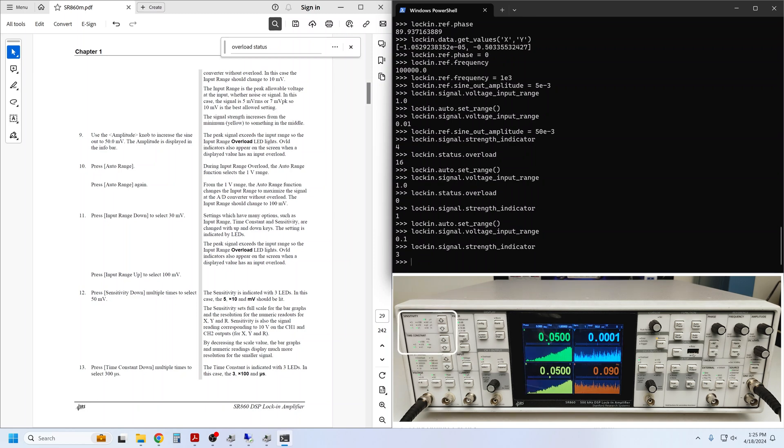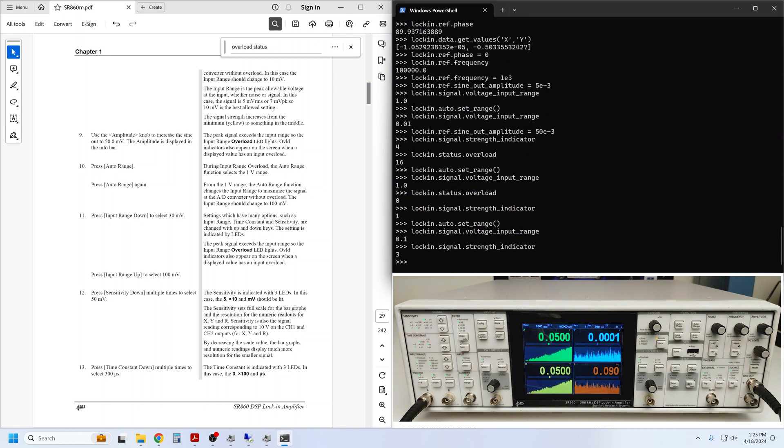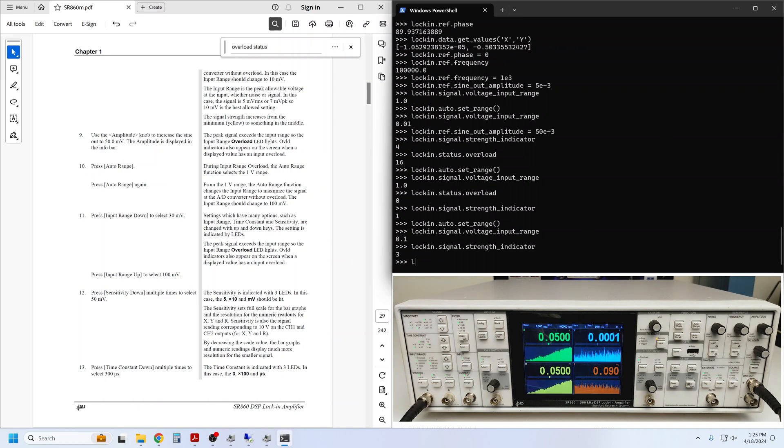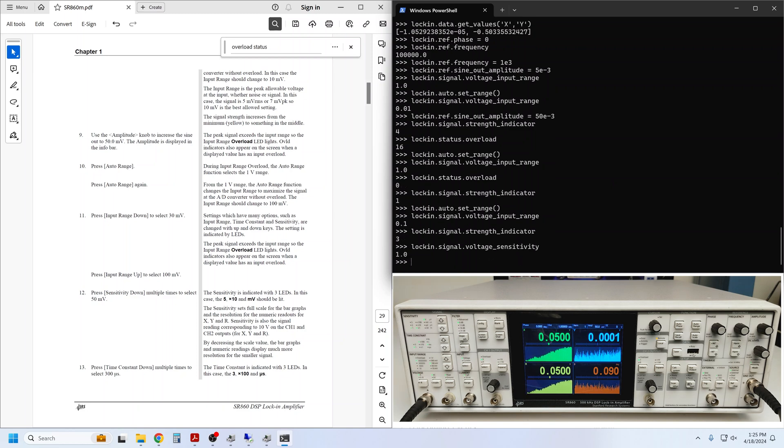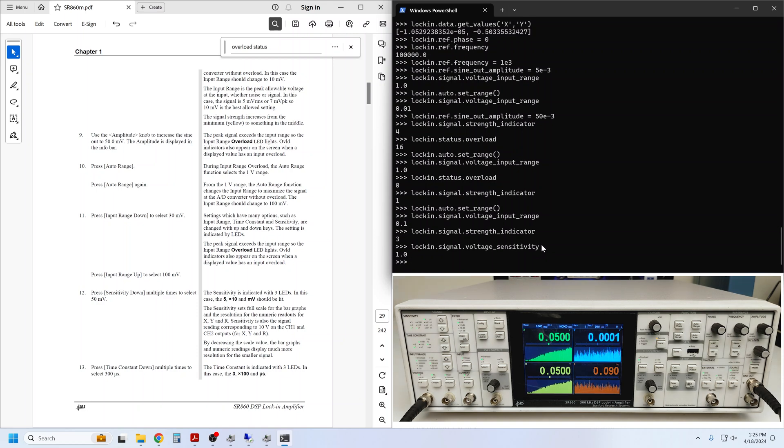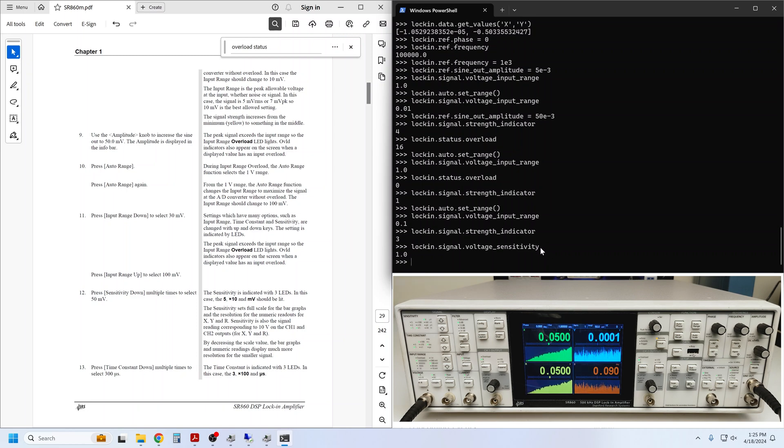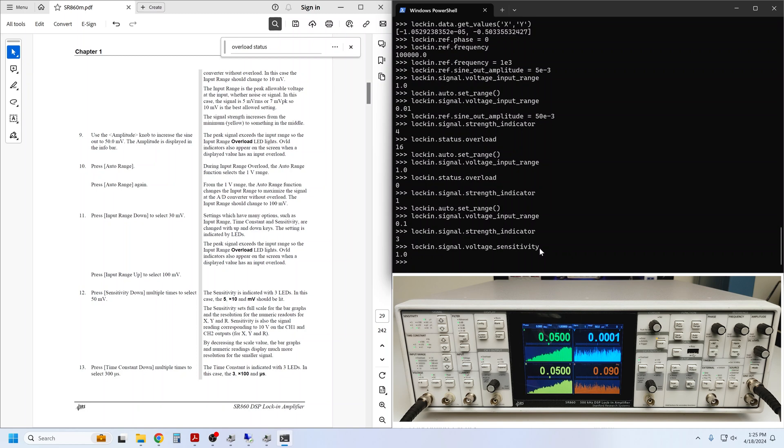Next, the Getting Started Guide walks us through changes to the sensitivity and time constant. By default, the sensitivity is set to 1 volt. That setting also lives in the signal component and is simply called voltage_sensitivity. This means that a 1 volt signal at the input would yield a full-scale 10 volt signal at the output. It also means that the front panel displays are scaled such that they could display a measurement result of at least 1 volt.